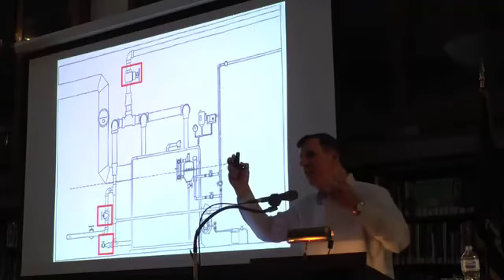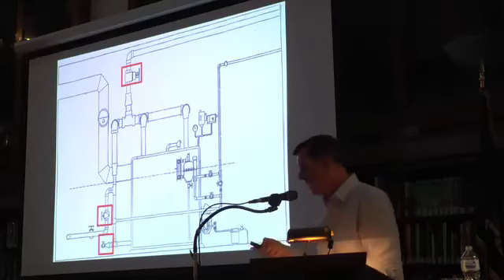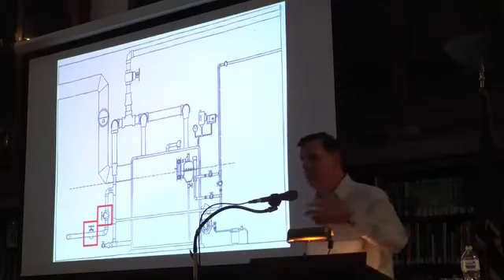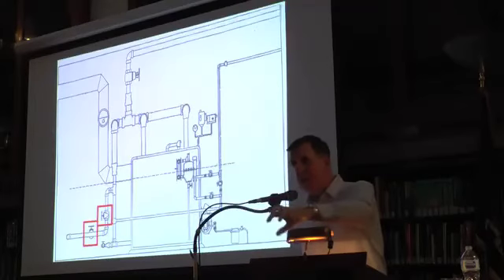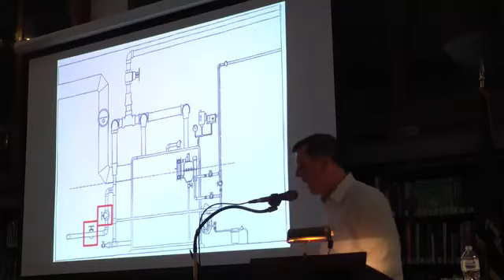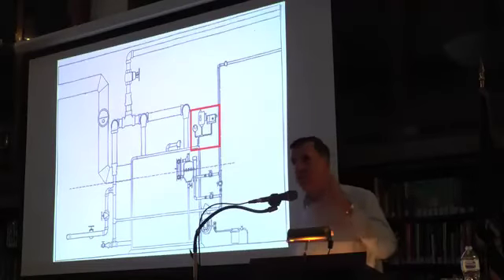Those two valves, you'll spend a little bit more money on to go in, but they will save that boiler. And it'll last for years and years. And while you're at it, on the return side, you put this drain valve there on the bottom too, so you can waste the condensate as it's coming back after you put the mix in. Shut the valve that goes back into the boiler and open the drain valve and just let that crap waste out of the boiler, so it does waste out of the system so it doesn't go back into the new boiler.